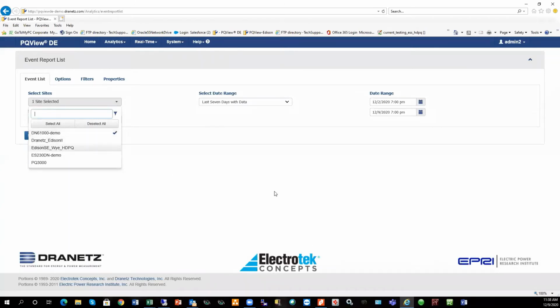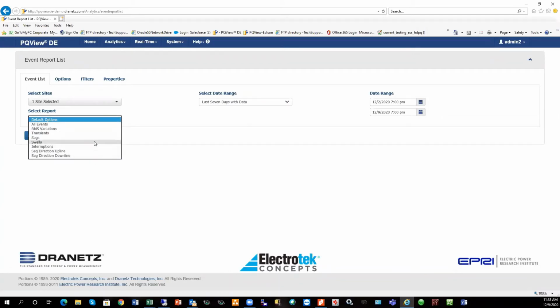Let's stick with our DNE1000 demo. We then select the type of report, so you can be selective. For example, if I'm simply looking for any SAG events, the most common PQ event that occurred upline, if these monitors are hung on our mains, the point of common coupling, so if I want to see if there's any SAGs that occurred upline, meaning from the utility, I can be more selective. You can think of this as almost like a filter. But let's go in and select all events for our demonstration.